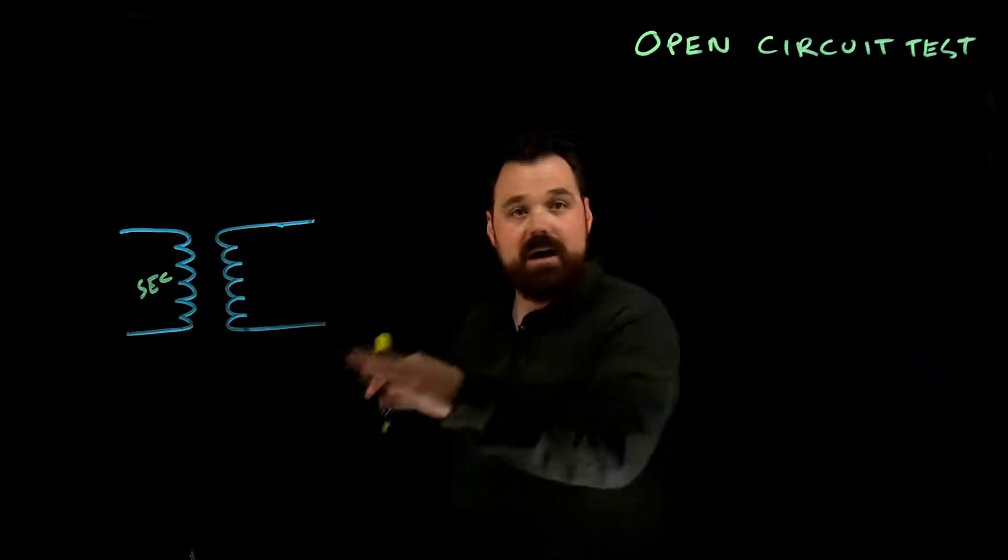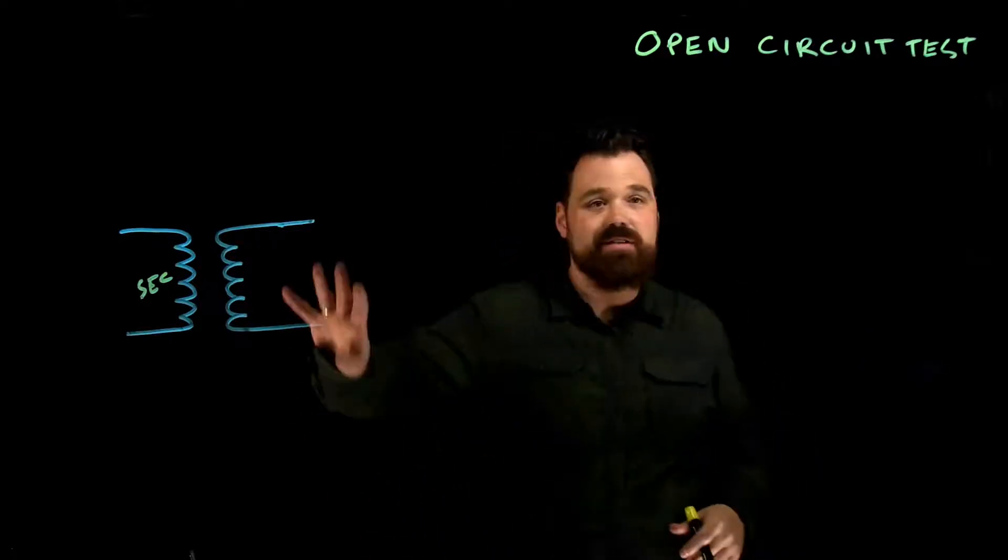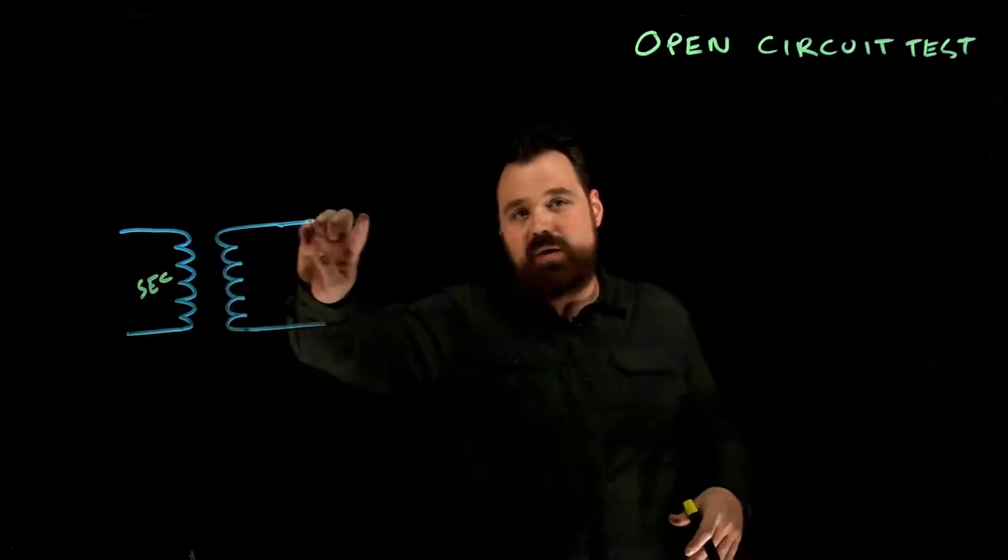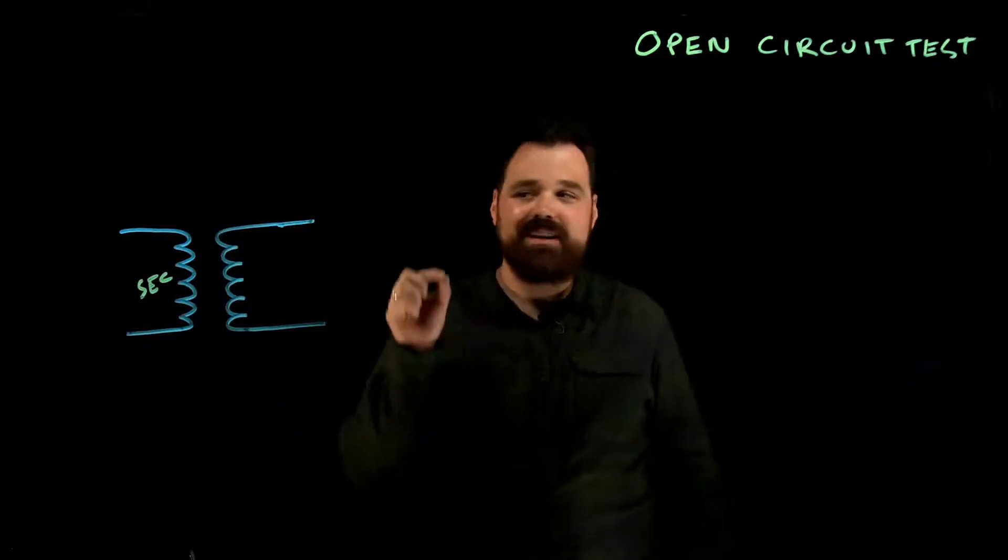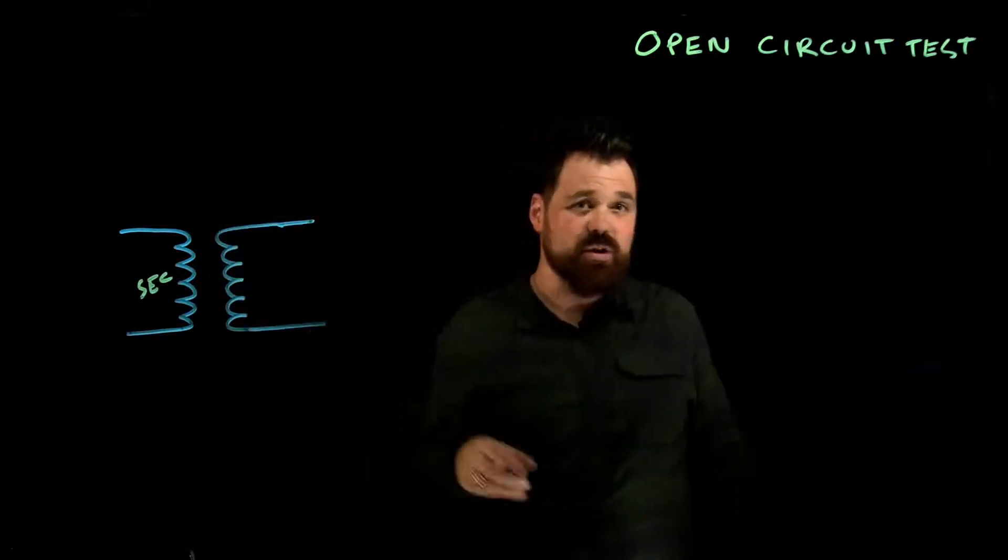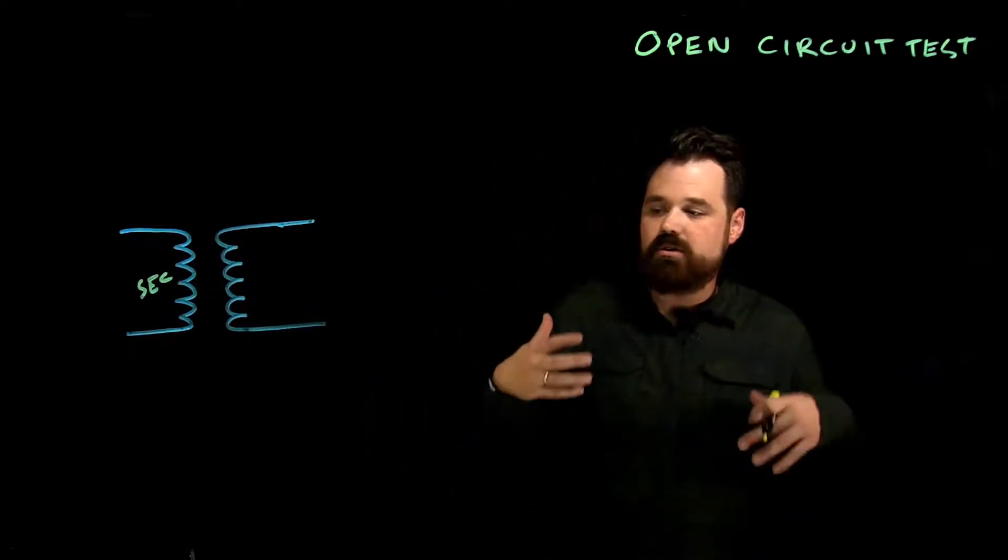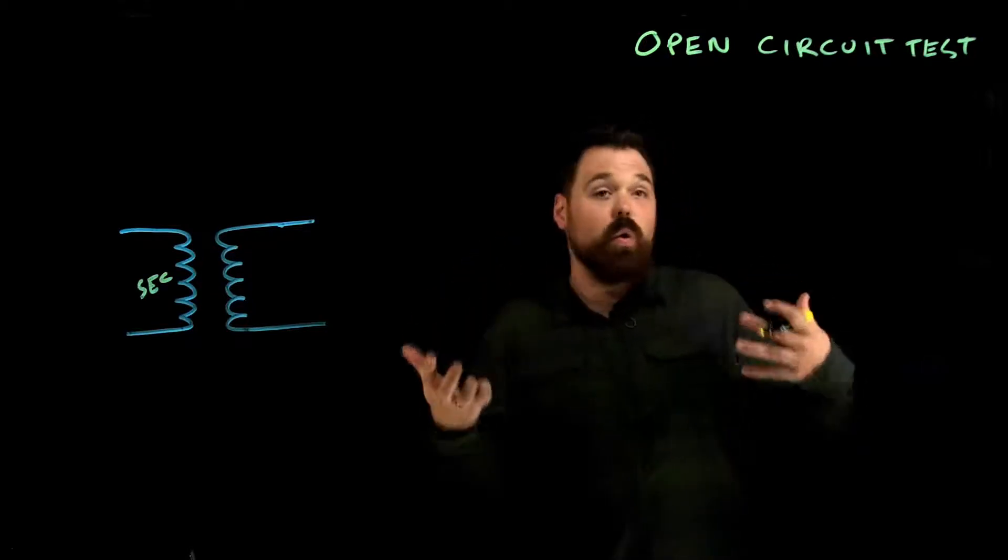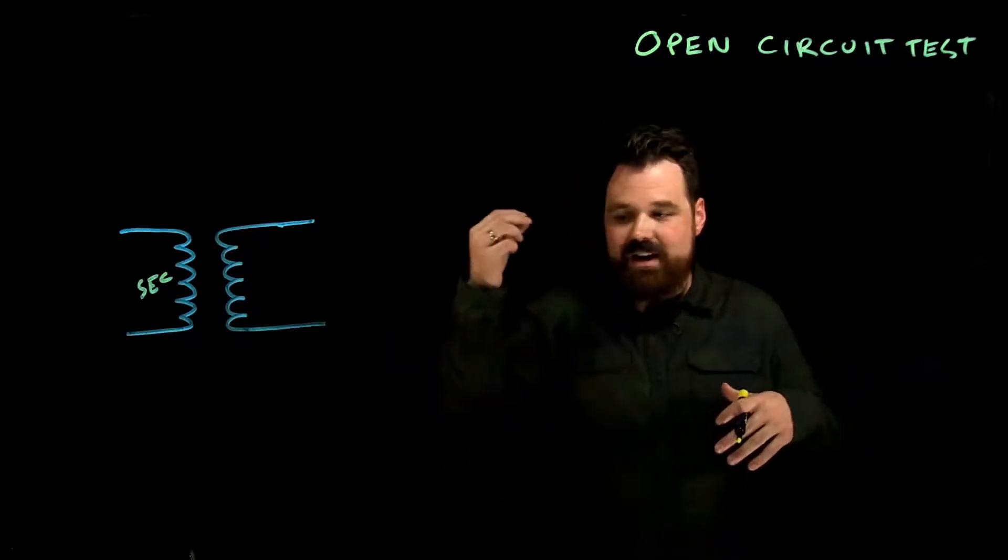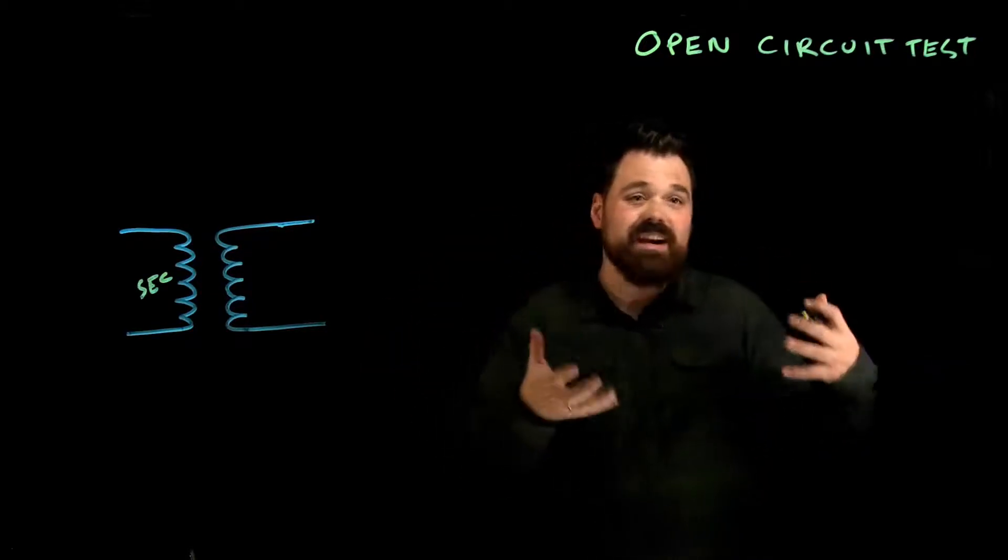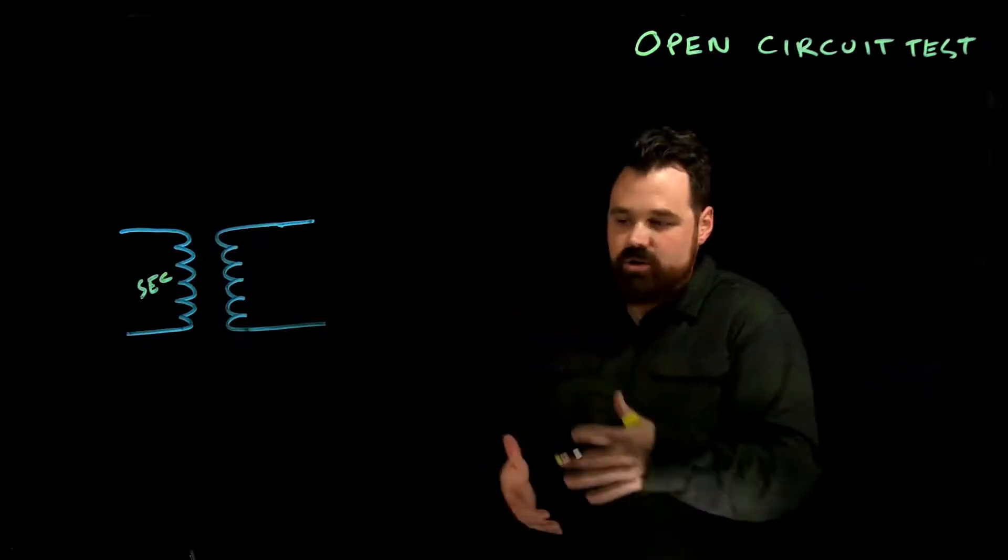So what happens when we energize a transformer with no load, the only current that's going to flow is the current required to magnetize the core. So it's the current required to overcome the core losses, hysteresis and eddy current, and it's the exciting current required to energize the core.